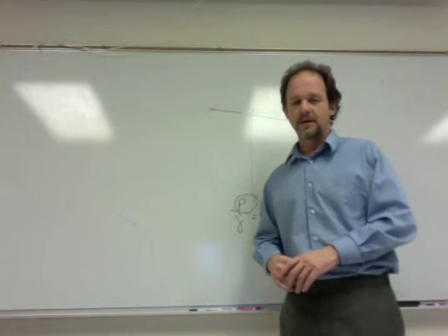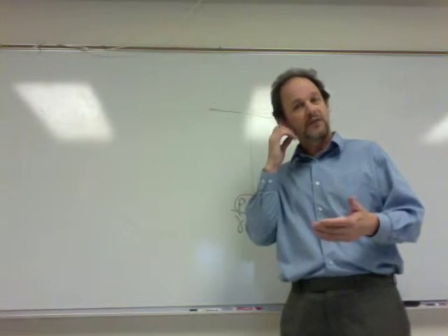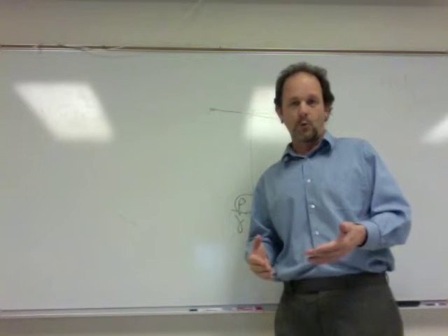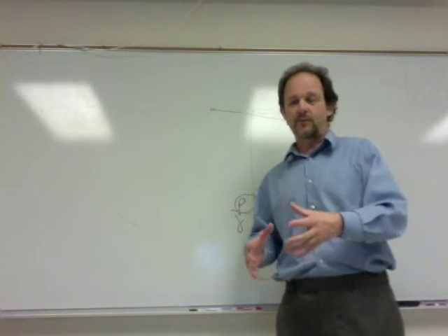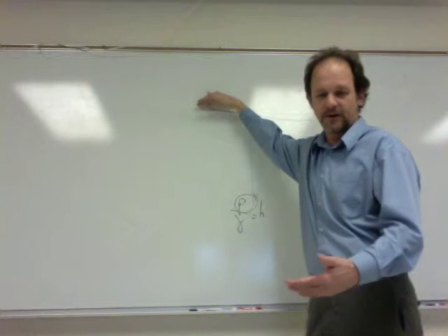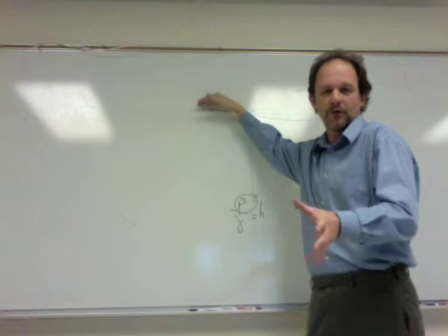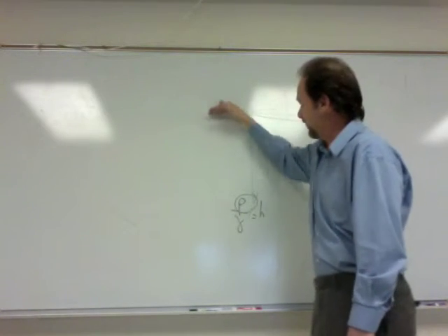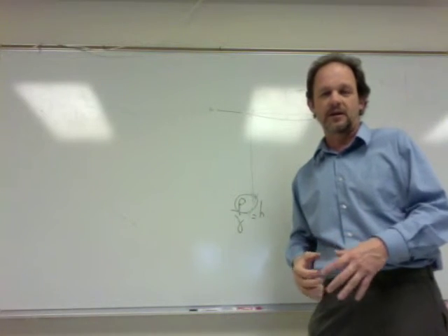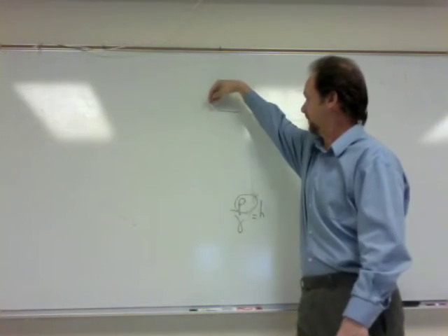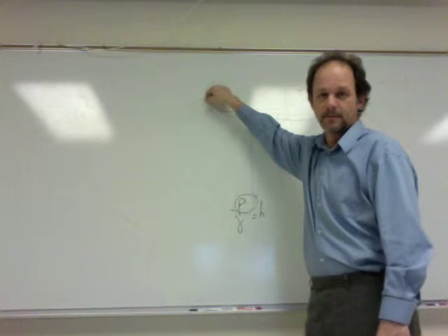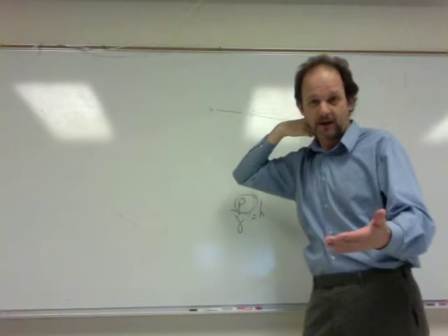All right, 37 is again converting everything to pounds per square foot and a Pascal's law problem, where you have some pressure up here, in the order of 60 psi, which converts up to about 130 feet of water, and then this other pipe is down below it, so you add up those two pressures. You add the pressure head from the pressure tank, which is in psi.